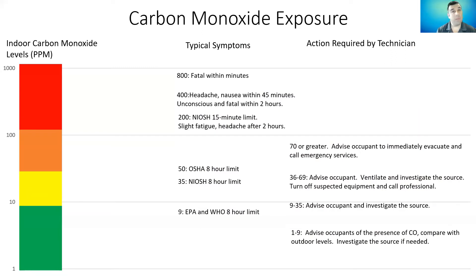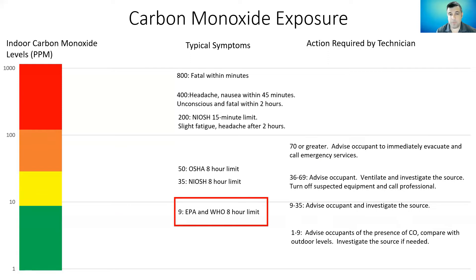At what levels is carbon monoxide unsafe? Carbon monoxide is measured in parts per million, and even by that term we can already see that it probably doesn't take a very high concentration to be unsafe. I always carry a personal carbon monoxide detector — a monitor clipped to my belt — and I monitor that as I'm walking through a space. At levels of one to nine parts per million, we're within the EPA and World Health Organization eight-hour limit, but really anything above zero should get our attention.